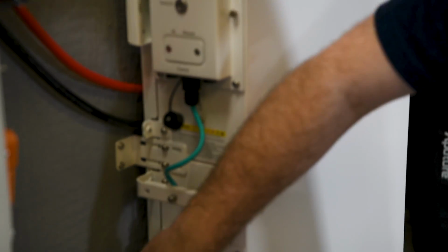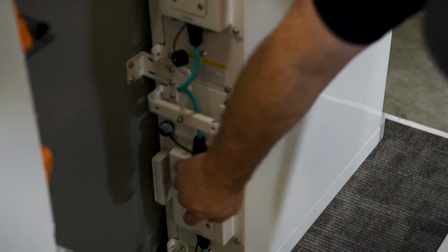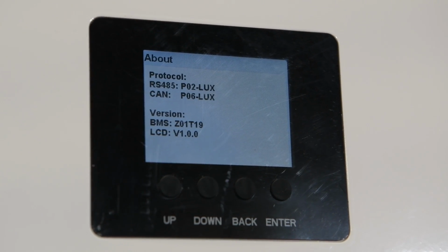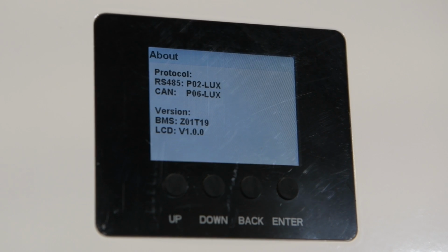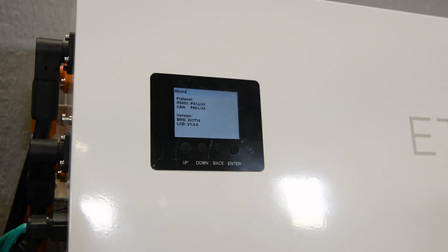Once the proper protocol has been selected, press back and then power off each battery module using the power button and then power them back on. Once this is done, the selected protocol will save once the controller box is turned back on. We can now see the proper settings displayed on the screen.